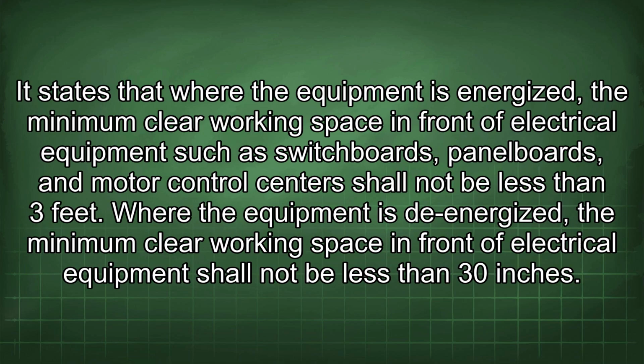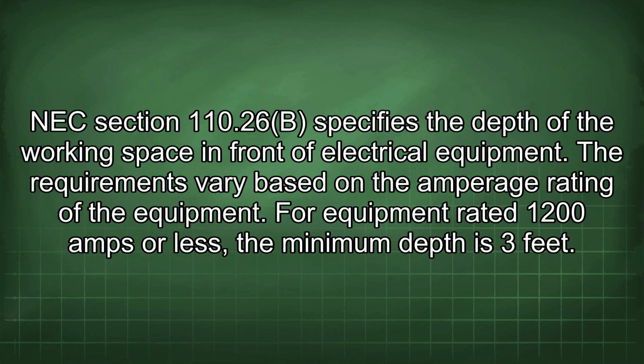It states that where the equipment is energized, the minimum clear working space in front of electrical equipment such as switchboards, panelboards, and motor control centers shall not be less than 3 feet. Where the equipment is de-energized, the minimum clear working space in front of electrical equipment shall not be less than 30 inches. NEC Section 110.26(b) specifies the depth of the working space in front of electrical equipment.